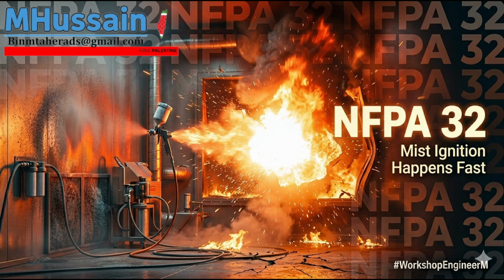That is a terrifying phrase. It really is. Spontaneous combustion in commercial laundry is a prime example of an invisible chemical hazard manifesting as a thermal event. How does that actually happen? It happens frequently with commercial linens, think towels from spas, restaurants, or industrial applications. These textiles retain trace amounts of unsaponifiable oils. Like massage oils or cooking grease. Exactly. Things the wash cycle doesn't fully remove.